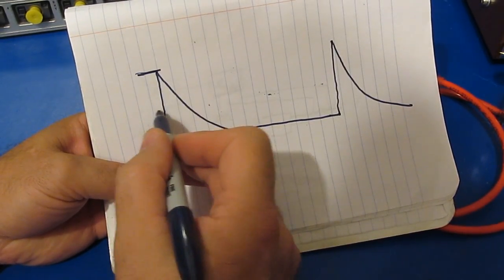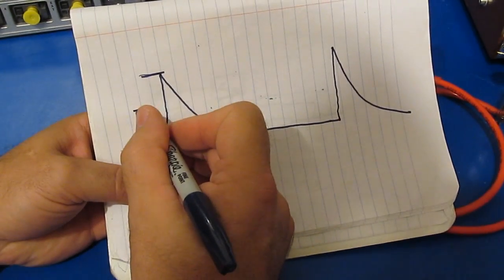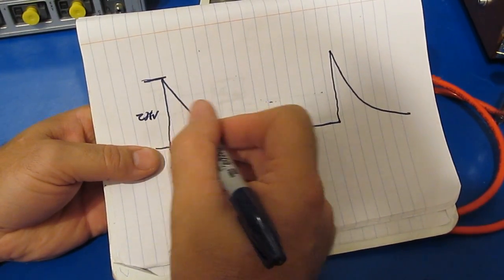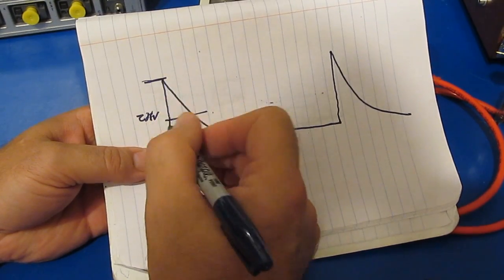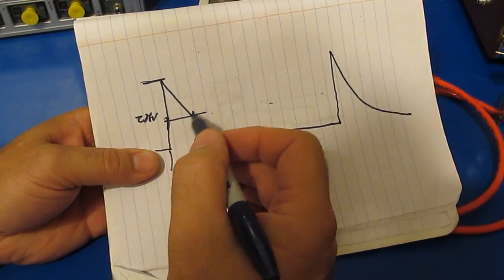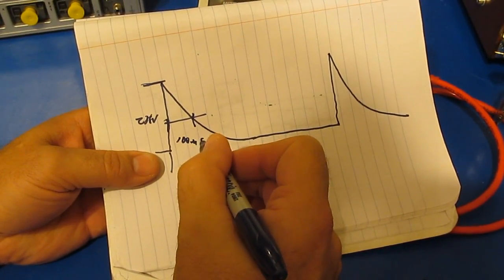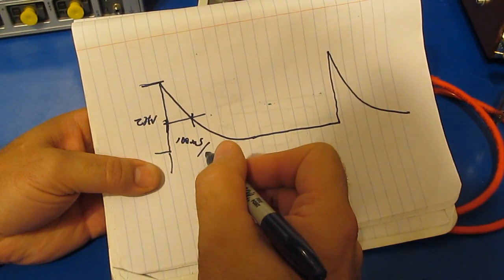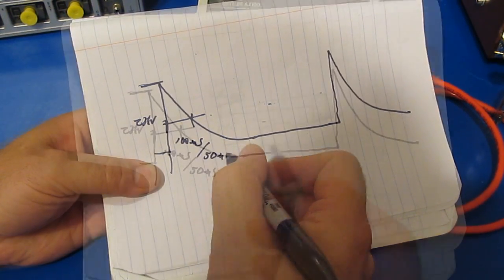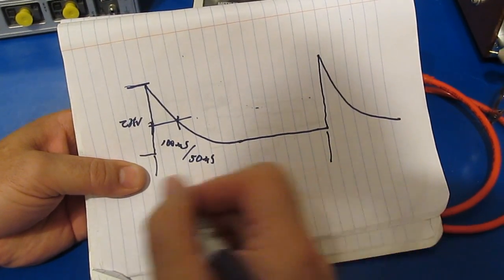Typically I'll give it five cycles of this spike. The way that I measure this spike is I look at the peak-to-peak amplitude here - that's for example 2 kV - and then I'll measure that at the half height. So if we divide that by 2 at 1 kV and measure how far it's decayed at that point, this will typically be in the hundred microsecond range. Then some tests I'll run at 50 microseconds. The rep rate is quite long, typically about five seconds between pulses, sometimes a little longer.